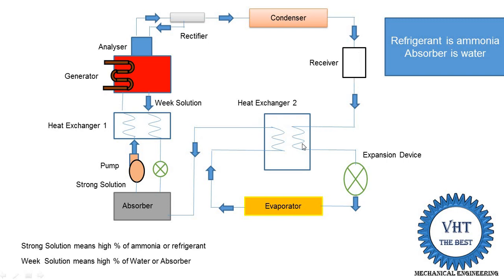We place heat exchanger 2 here between the condenser and evaporator, where heat is exchanged between the liquid refrigerant coming out from the receiver and the vapor refrigerant coming out from the evaporator. Heat exchanger 2 works as a sub-cooler. It reduces the temperature of the liquid refrigerant coming out from the condenser or receiver, which increases the refrigerating effect in the evaporator. The vapor refrigerant leaving the evaporator has its temperature increased, and then it is supplied into the absorber.